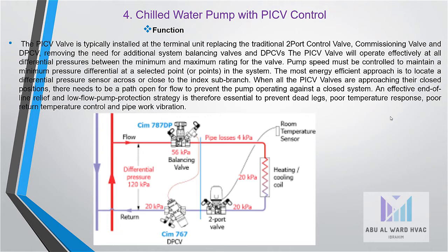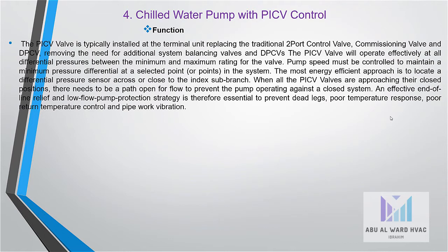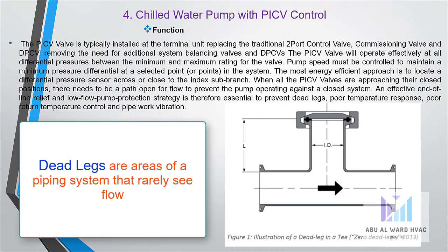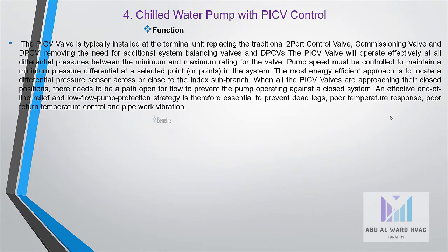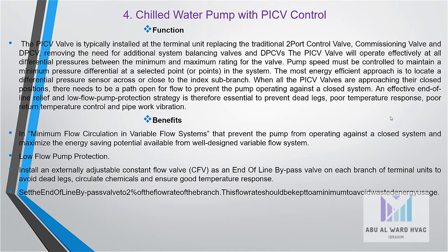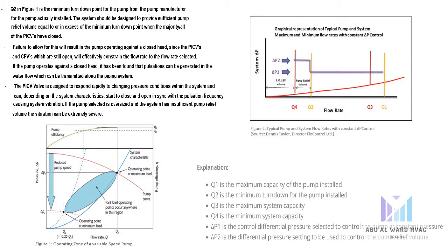When all the PICV valves are approaching their closed positions, there needs to be a path open for flow to prevent the pump operating against a closed system. An effective end-of-line relief and low-flow pump protection strategy is therefore essential to prevent dead legs, poor temperature response, poor return temperature control, and pipe work vibration. Benefits: in minimum flow circulation in variable flow systems that prevent the pump from operating against a closed system and maximize the energy saving potential available from well-designed variable flow system.